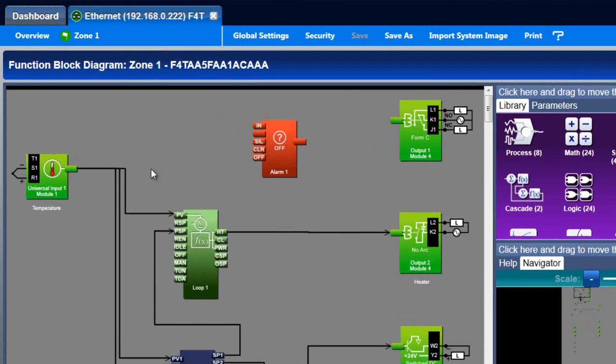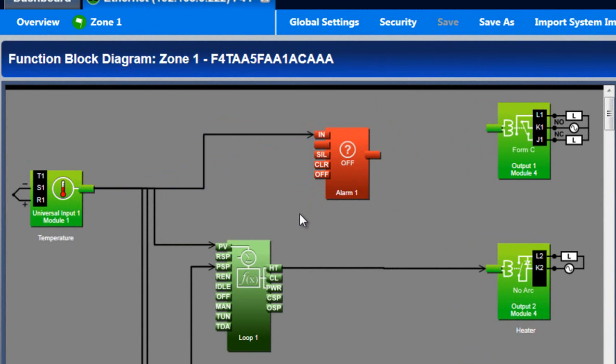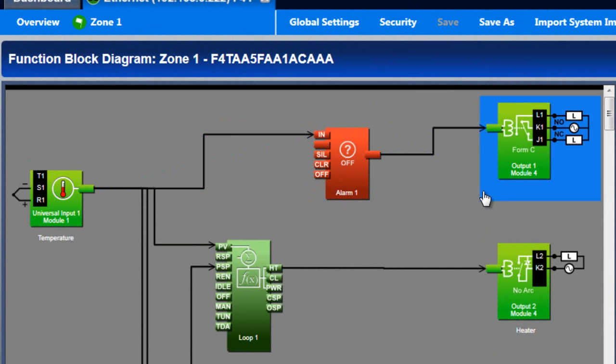Connect the analog signal you want the alarm to monitor to the IN receiver. Here we use the same input signal that loop1 uses for control. To make something happen when an alarm occurs, connect the alarm's transmitter to another function block. Here I connect it to an output.